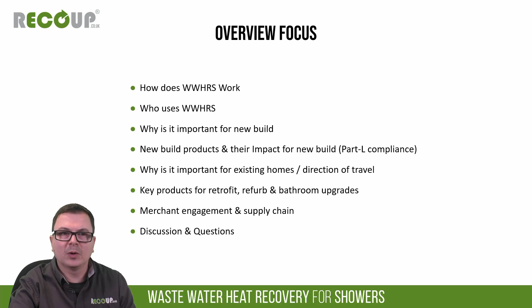So we'll start with the very, very basics: how does wastewater heat recovery work? If we look at the standard showering configuration, in this case a thermostatic mixer shower, you've got the water heater, be it a combi boiler, an instantaneous water heater, an unvented cylinder, HIU, whatever it may be, creating that domestic hot water up to around 55, 60 degrees to go off to the thermostatic mixer shower. Then at that point, a cold main is introduced to be the cold side of the mixer shower, to take it down to a more pleasant showering temperature, around 40, 41 degrees.